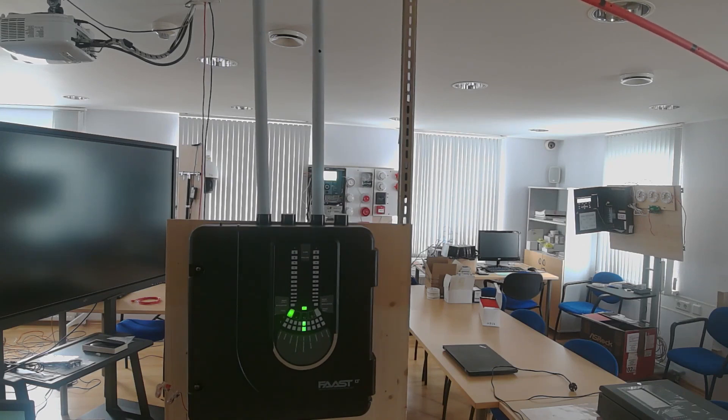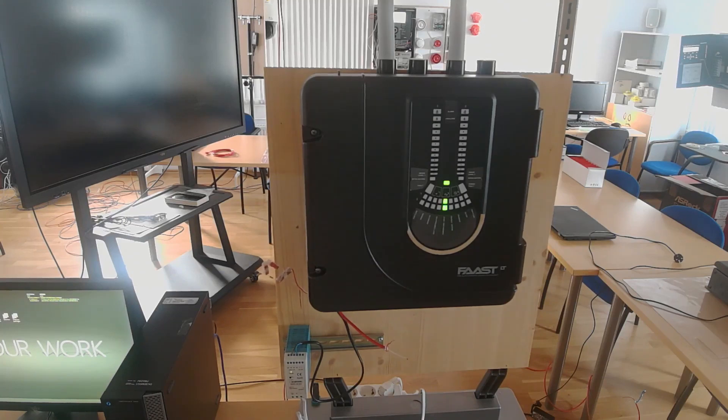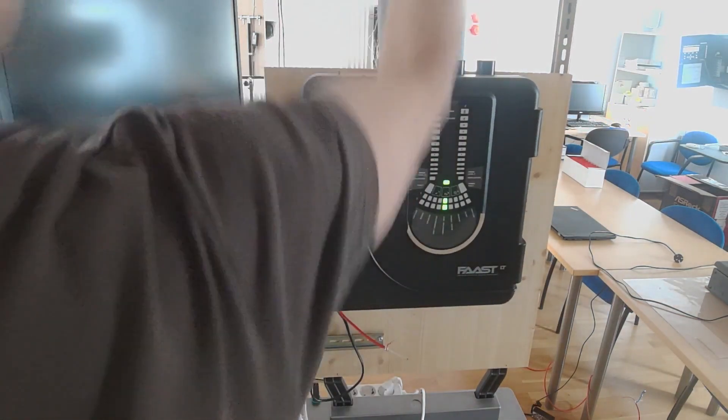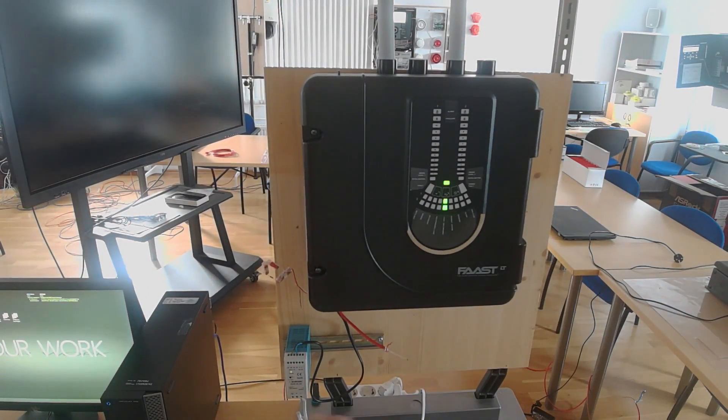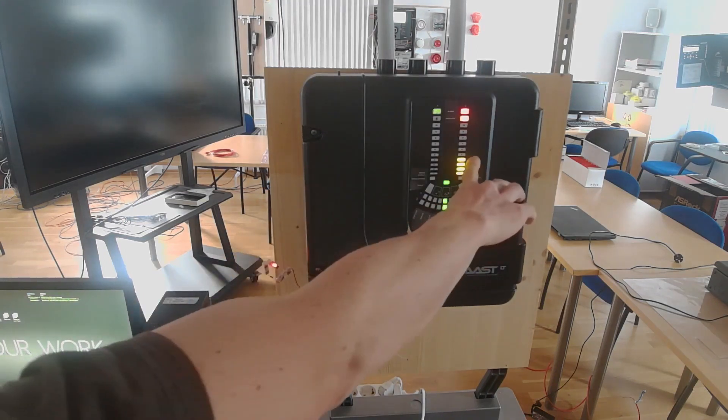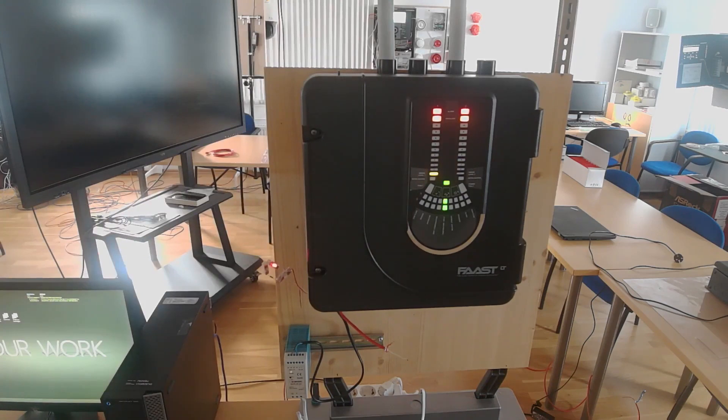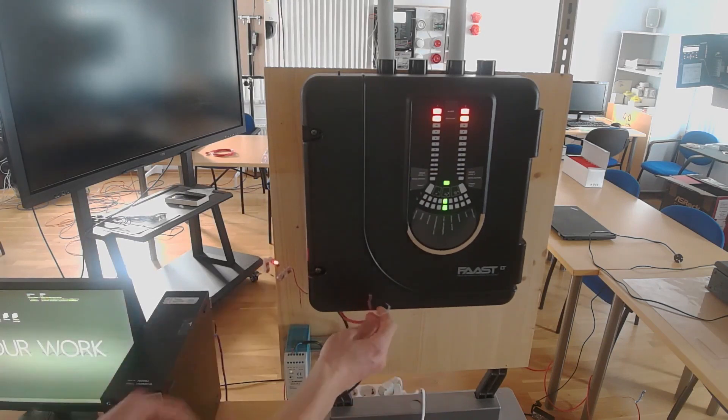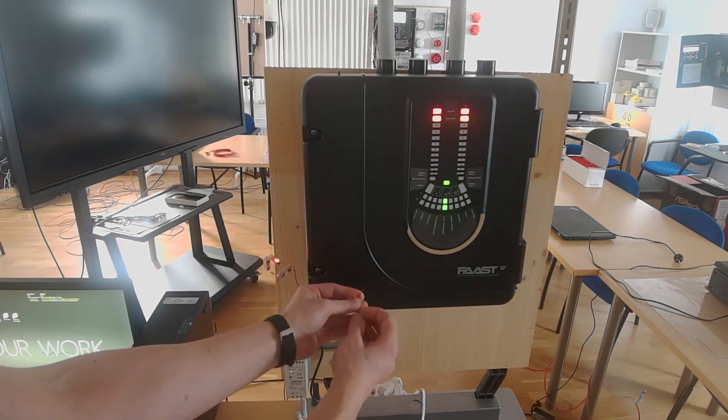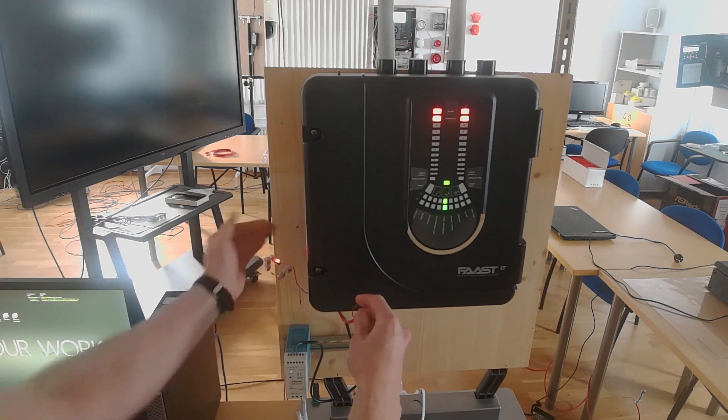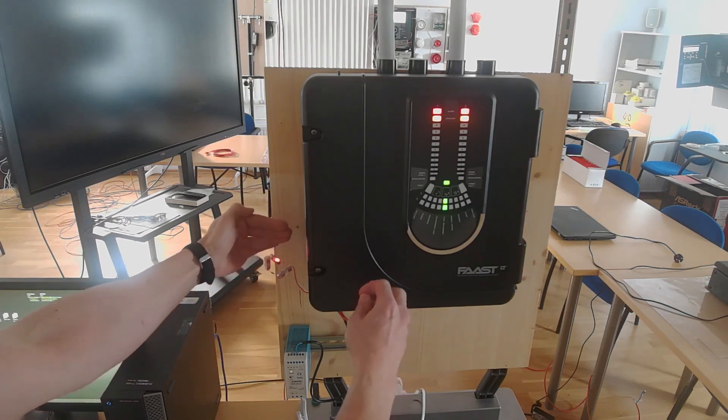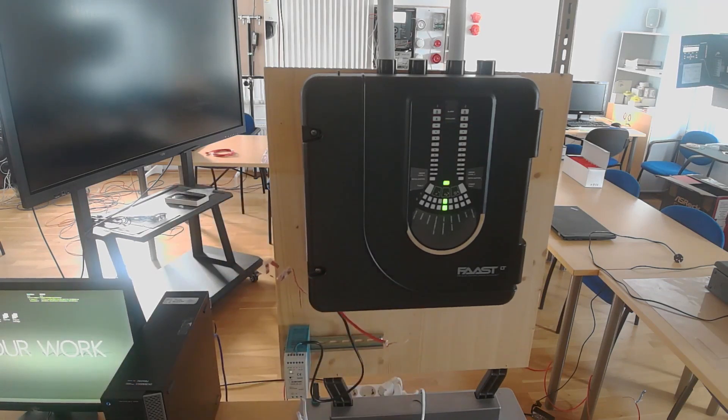I finished up showing the device in work. I also will try to reset device by external input. What have I done? Then the fire. Fire is level three. Let me wait until it gets to zero. The second channel also sends the smoke. Smoke level is gone now. And now I can reset. So, I will use external reset. I have only two wires, but you can make some button or whatever. And if you see, I have LED that is telling me that the detector is in fault condition. Now I will reset it by external input. Yep, that is working.